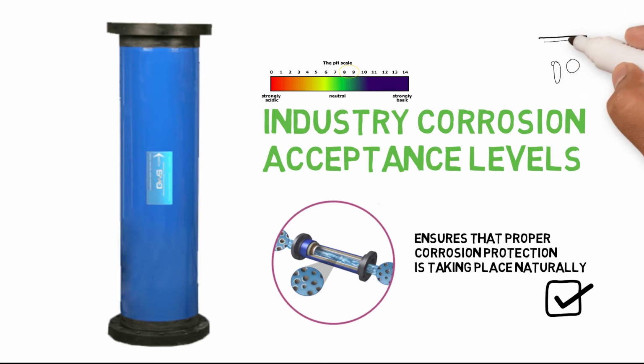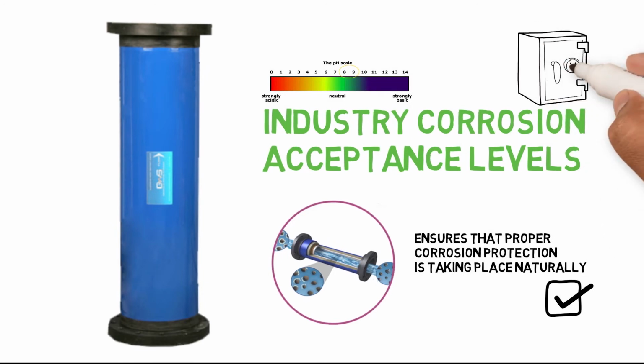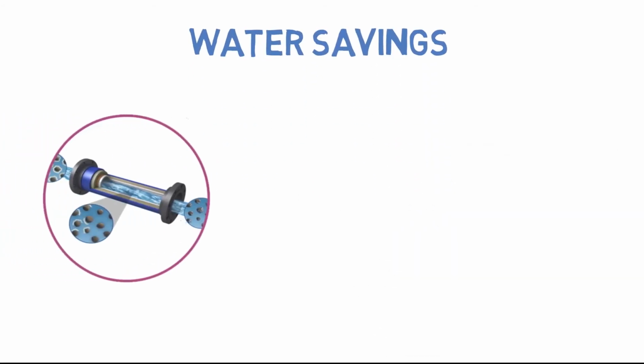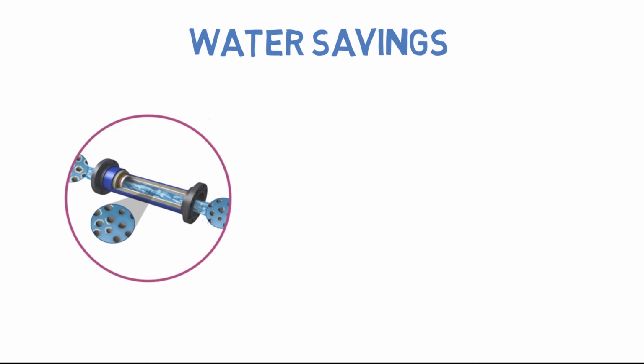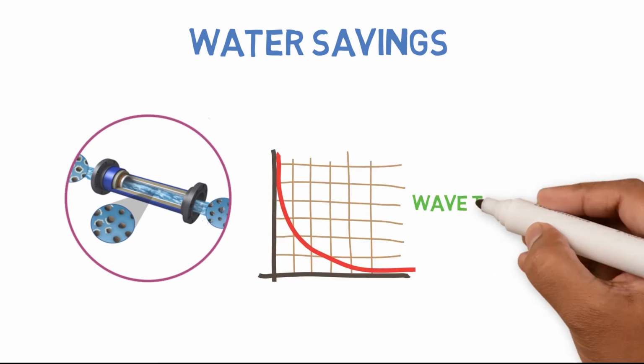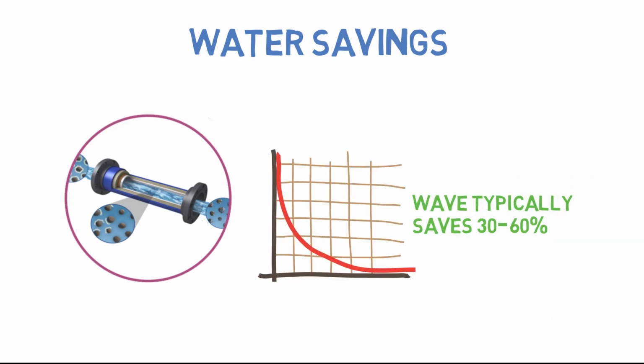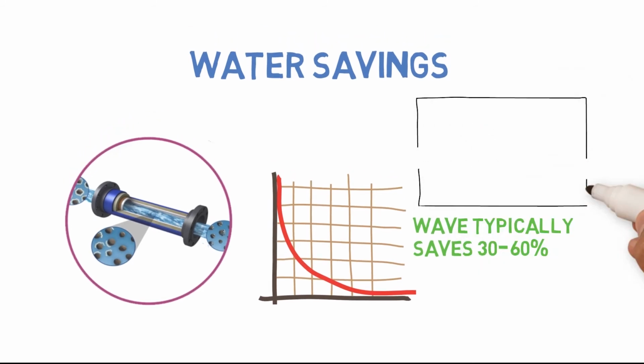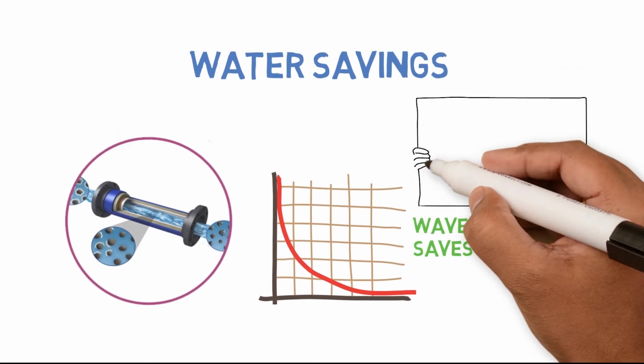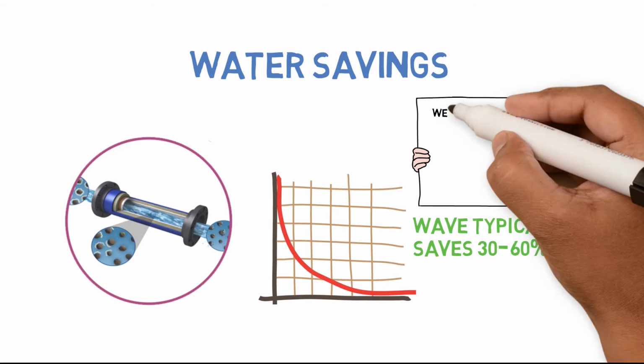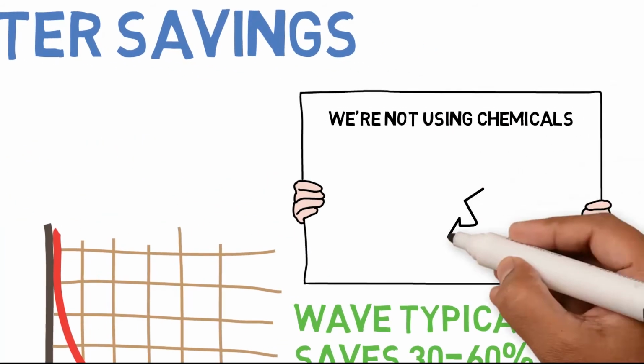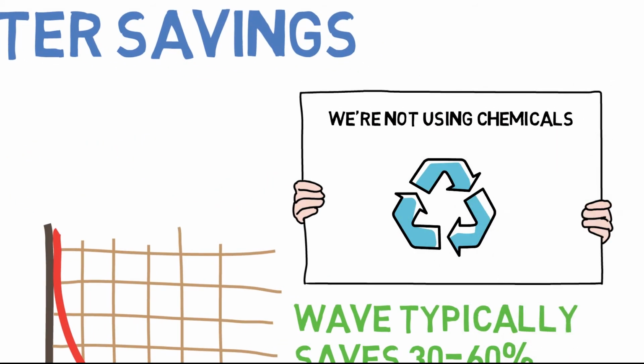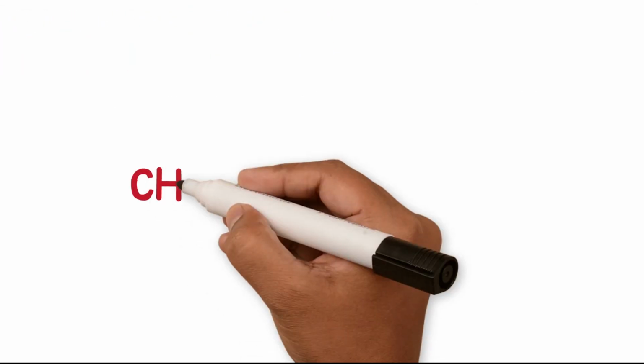The Wave non-chemical water treatment system makes the most financial sense. Number 1, water savings. Because we do not need to continuously flush down and dilute chemicals and minerals, the Wave typically saves 30 to 60% compared to chemical systems. In most regions, our non-chemical treated water does not need to go to the sewer, and sewage fees are saved. Because we're not using chemicals, we can reuse the blowdown water for landscaping and other purposes and realize this additional water savings.